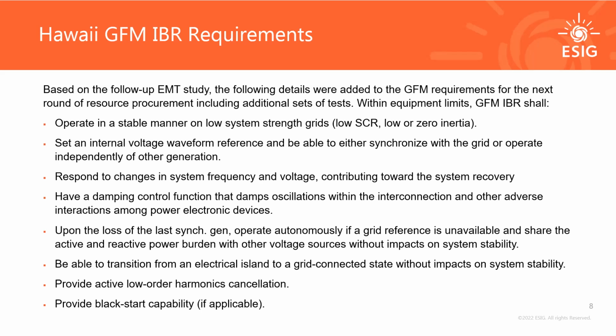These are high level, with similar themes to what you've seen for National Grid. Operate in a stable manner in a low short circuit strength system. Set an internal voltage waveform reference, and either synchronize with the rest of the resources on the grid or operate as an island, like just operate a grid that has this one grid forming inverter there. Respond to changes in system frequency and voltage, which is similar to instantaneous active and reactive power injection in response to different disturbances. Provide damping. If the last synchronous generator is lost, it has to continue operating in a stable manner, synchronizing with other grid forming and grid following resources on the grid, or operate as part of the system as an island. Be able to transition from electrical island to grid connected and back, cancel low order harmonics, and provide black start capability if applicable. Not all of these resources are expected to provide black start capability, only some, similar to how currently not all synchronous generators are black start capable, only a subset of them.